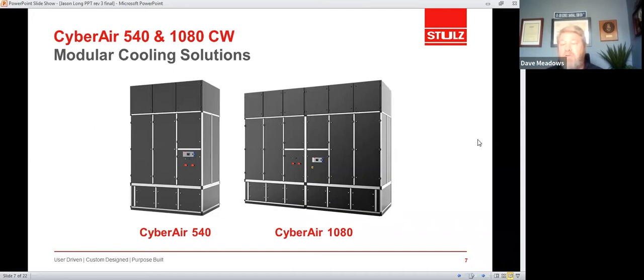And then its big brother is the Cyberair 1080. This is a massive unit. It's moving 96,000 CFM against 0.2 inches of external static pressure, doing over a megawatt of cooling, so somewhere around 307 tons at ASHRAE Class 2 return air conditions. It is currently the largest computer room air handler on the market.